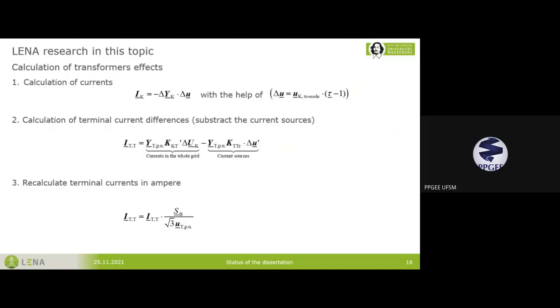Based on the voltage difference between the two nodes, created by the step of the phase-shifting transformer, you can calculate these current sources, then superpose the currents of the whole grid with the currents created by these additional current sources, and calculate the effects the PSTs will have on the overall grid. Since this whole approach is done in per-unit values, you have to recalculate the currents into amperes, and can then define the current deduced directly from the phase-shifting transformer.